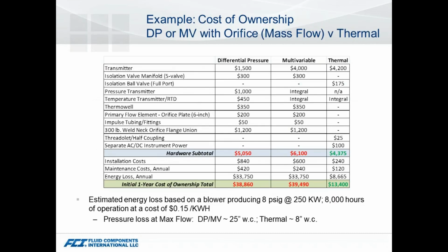But one thing to look at when you see these capabilities, comparing to an orifice, for example, from a cost standpoint, everything's fairly even. There's a little bit of an edge for thermal if you look at just basic costs of all the accessories you need to purchase. But the big savings is going to come in your energy loss, your permanent pressure loss. So when you look at cost of ownership, you've got to take that energy loss into account to really get your true overall costs. A lot of times I think we don't look at that closely. There's some definite savings from an installation standpoint, from a single process point, but this gives you that overview of the value thermal brings to your measurements, not only in performance, but in overall ownership costs.